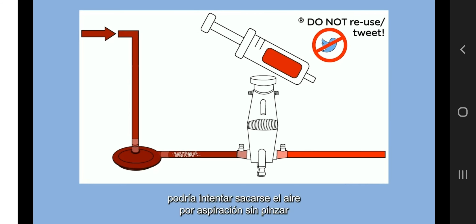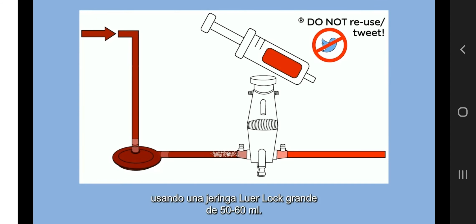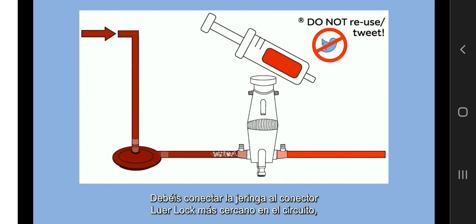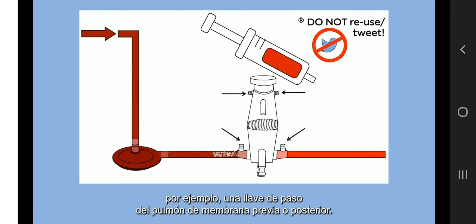If you have a really small amount of air before the membrane lung, you could try to remove the air through aspiration without clamping the return line and without interrupting blood flow, so without interrupting extracorporeal support, using a large 50-60 milliliters Luer lock syringe. You need to connect this syringe to the nearest Luer lock connector on the circuit, for example, a pre or post membrane lung stopcock. And you need to try to aspirate air.